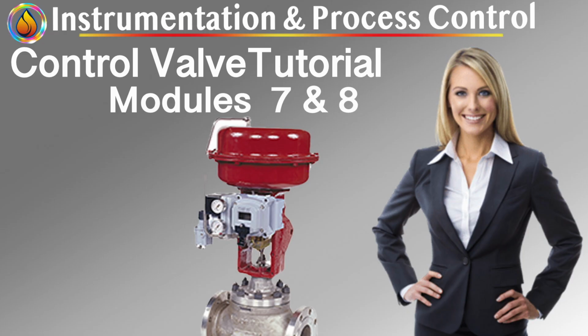Why actuator plus positioner must be treated as one system. A positioner cannot be evaluated independently. Key system interactions. Actuator volume affects response time. Supply air pressure limits available acceleration. Valve friction dictates required gain. Process speed defines acceptable dynamics. Treating the positioner, actuator, and valve as separate components leads to over-aggressive tuning, hidden oscillations, and poor disturbance rejection. Treating them as a single dynamic system allows predictable response, stable high-gain control, and reduced maintenance-driven variability.